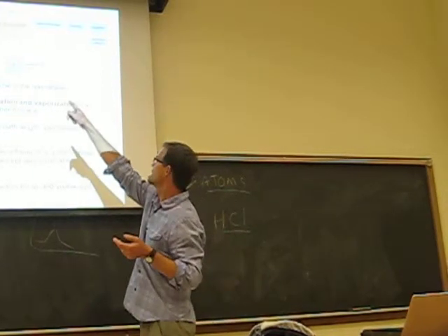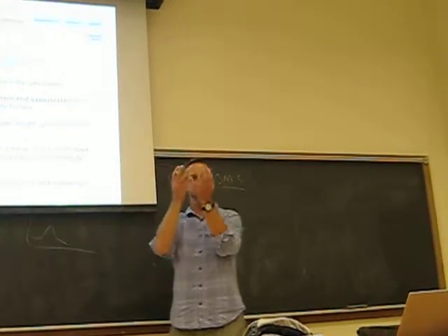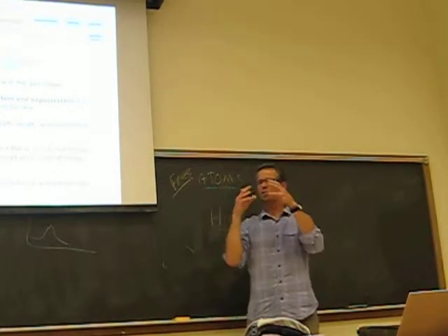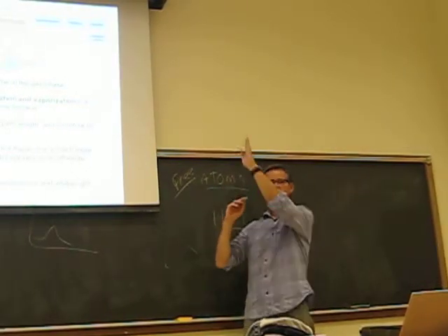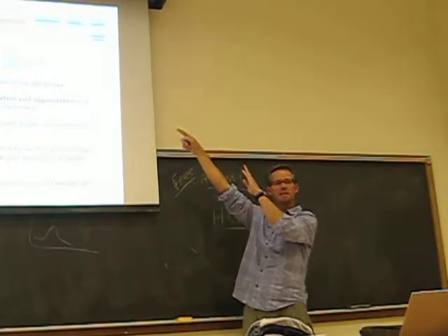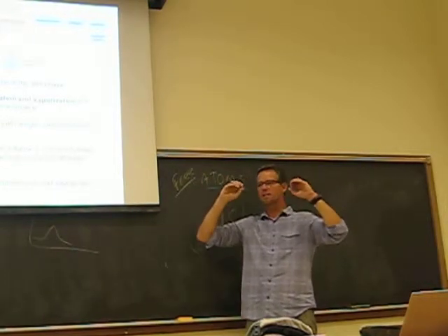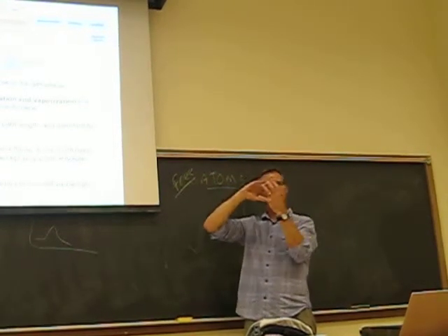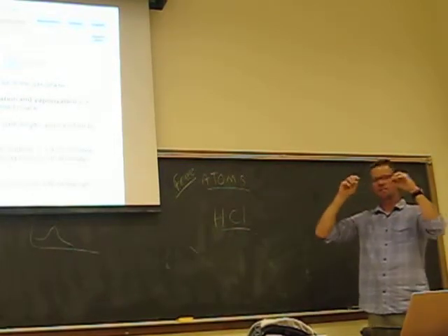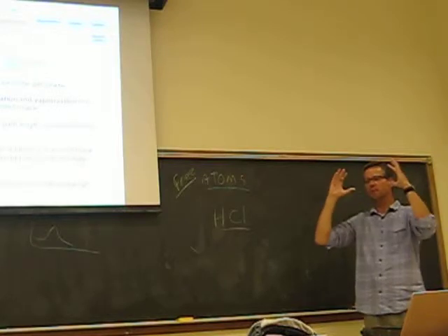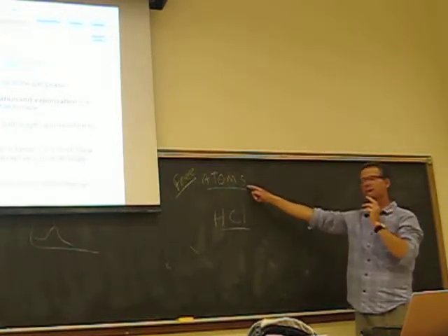Then that selected light passes through my sample, which has been sucked up into this instrument and turned into a mist in air, and then that mist is introduced into a hot flame, an air-acetylene flame in your case. And now the heat in that flame causes the atoms in that mist to evaporate, desolvate, and break apart if they're molecular species, and generate a gaseous state of the free atoms.